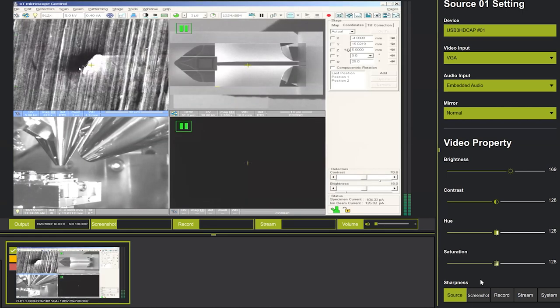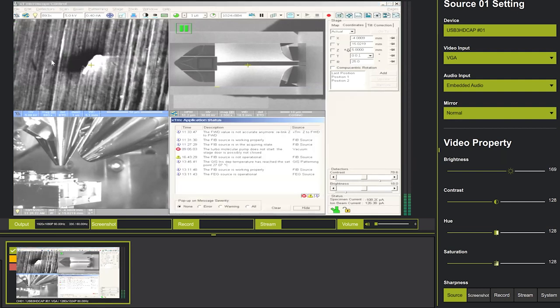This is the typical working environment. The working distance at the eucentric height should be about 5 millimeters for this instrument. This is the electron beam pole piece, and this is the ion beam pole piece. Right now I'm looking at the sample top down with the electron beam. For the milling environment, I want the ion beam hitting perpendicular to the surface, which means I have to tilt the stage—tilting toward the ion beam, but by a smaller amount.